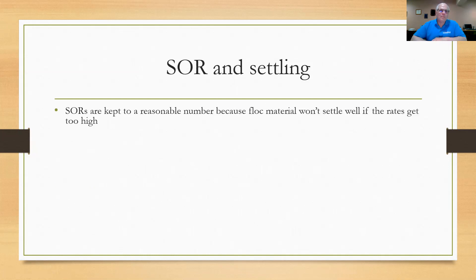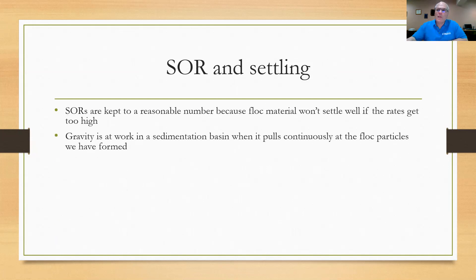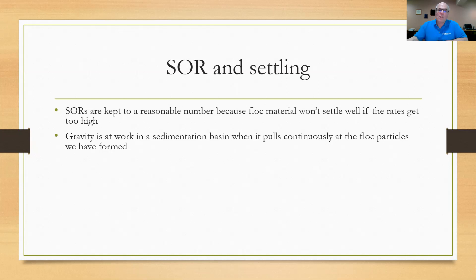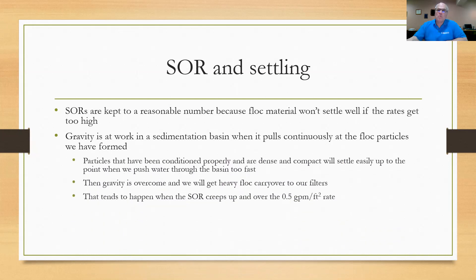Surface overflow rates are kept at a reasonably low number because floc material is not going to settle if our rates get too high. That's why we want to know how to calculate surface overflow rate — it tells us if the floc is not going to settle properly. Gravity pulls down on the floc particle continuously, but we're going to overcome that if the flow through our basin is too aggressive. Particles settle because they're dense and compact, up to a point. When that point is reached, things won't settle properly because we overcome gravity when the surface overflow rate creeps above 0.5 gallons per minute per square foot.